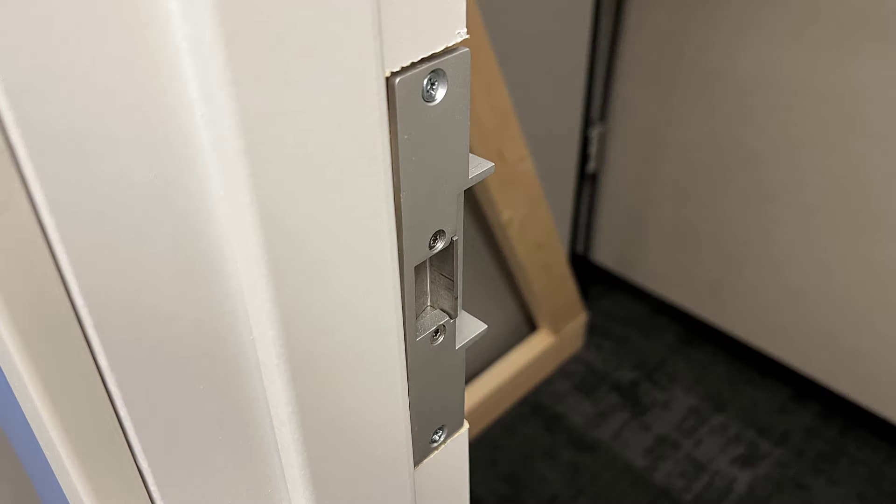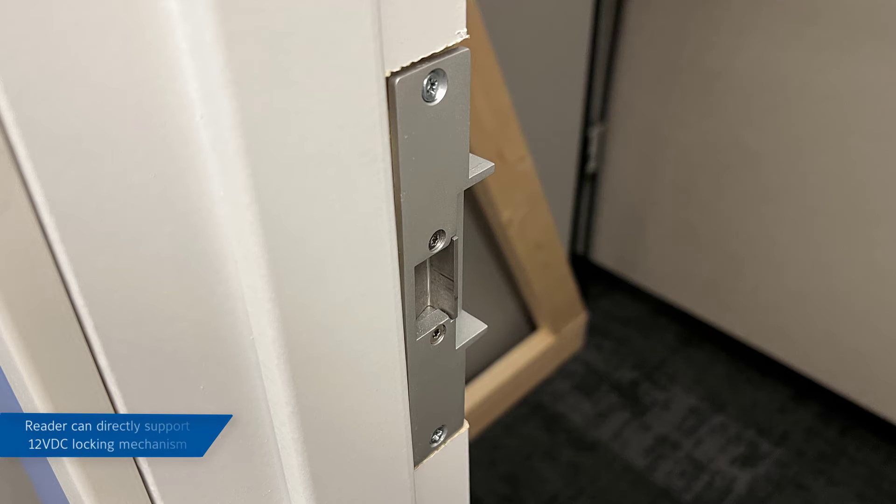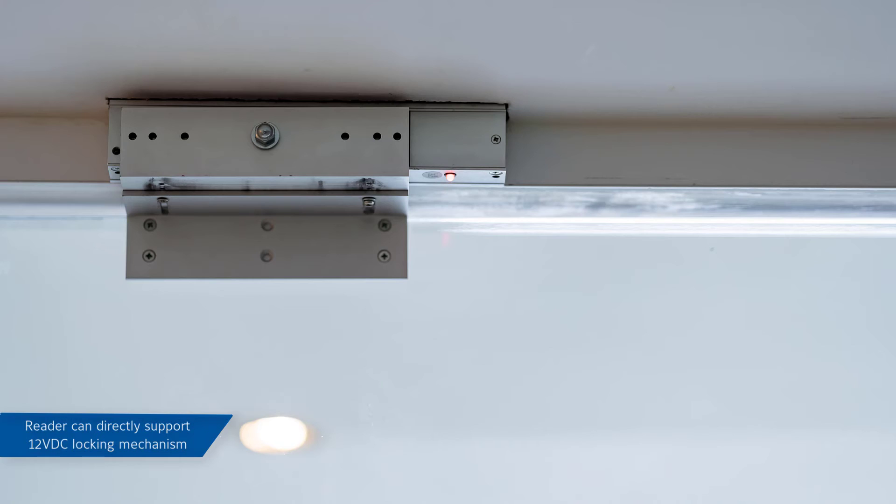Note that the reader can directly support a 12-volt locking mechanism and can be configured for fail-safe or fail-secure operation. If your lock requires higher voltage, you should use an isolation relay between the reader and the lock.